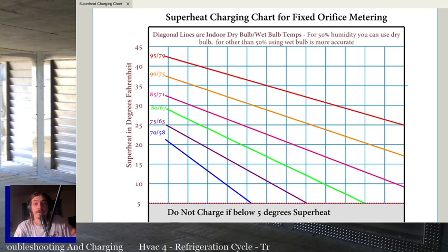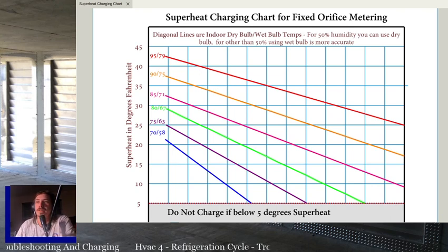You don't have to pull everything out and evacuate it, especially, like I said, if you don't think there's non-condensables in there and it looks good, then just pull out enough that you're close to zero and you have a good idea of where the charge is at, weigh that back in, and get it close enough that the charge shouldn't be what's screwing you up. Does that make sense? All right.